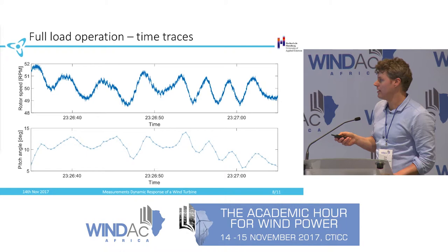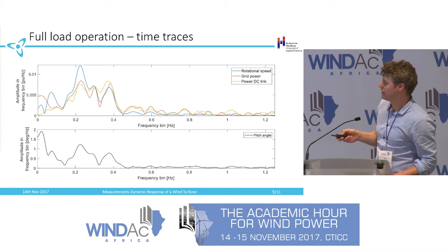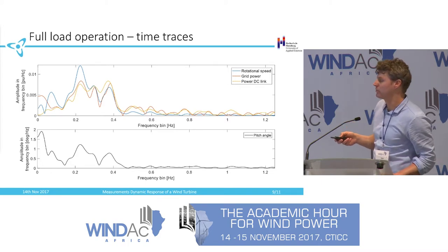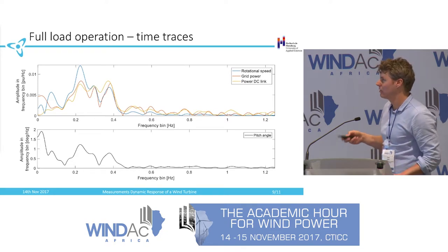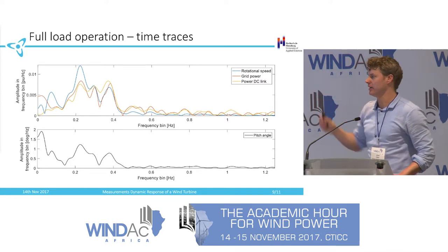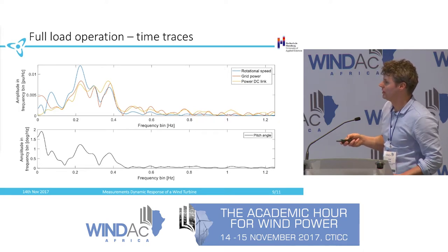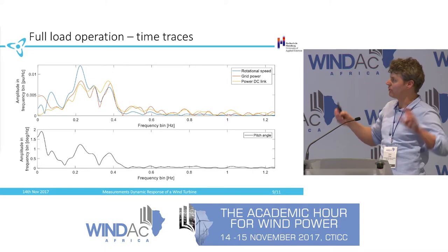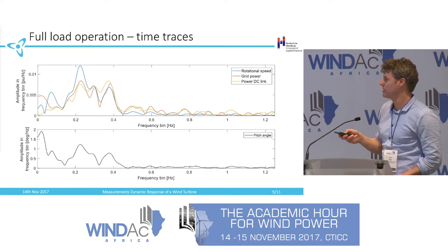And if we look at that in the frequency spectra, we basically see that these effects are hardly dampened. So if we're here at full load or close to full load operation, there's less space for dampening for us. And we see that the peaks here, so the pitch angle tries to catch the rotational speed, make it stick to 50 RPM, but it doesn't manage to do that. And that's why these peaks are matching these peaks here.